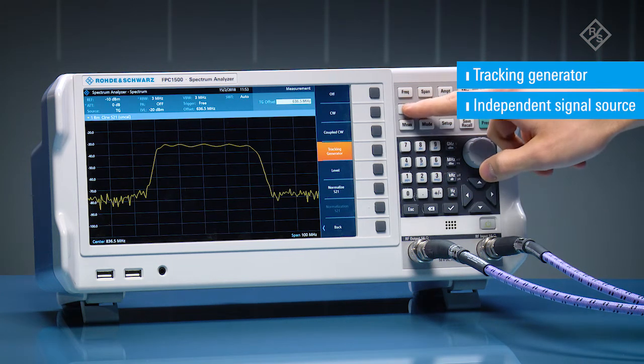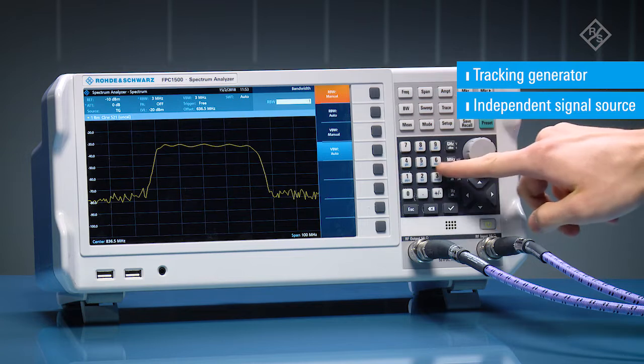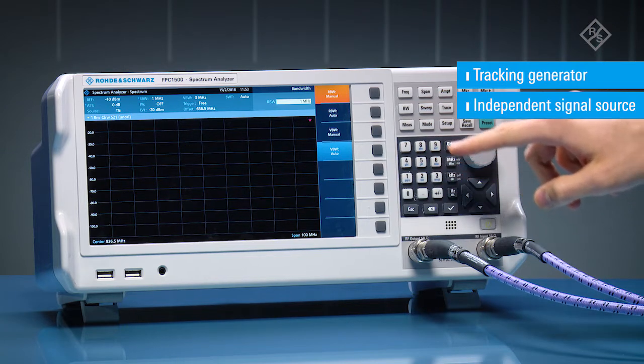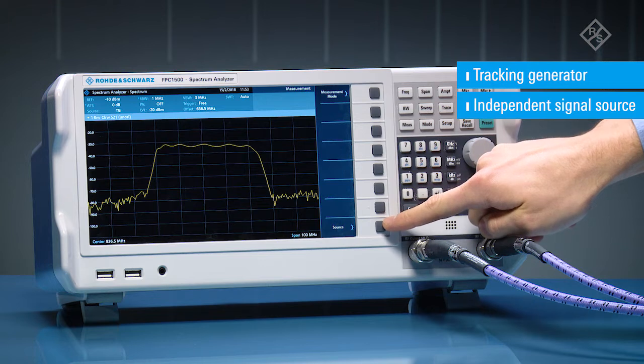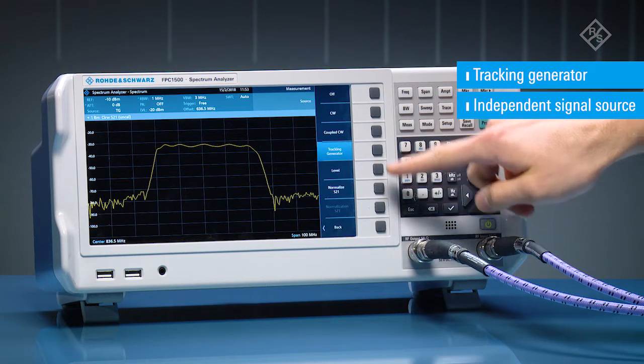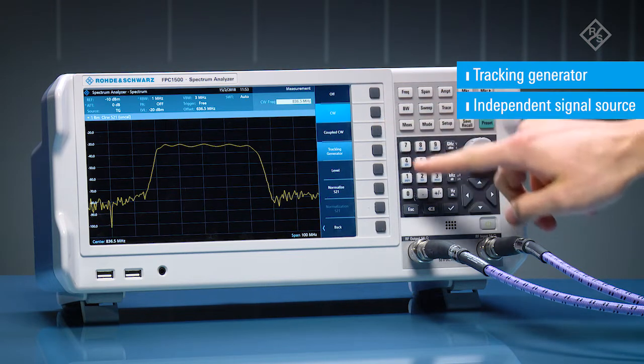The unique independent signal source of the FPC-1500 also supports signal generator functionality. Two different modes are available. One mode is used to configure a CW signal as required for the measurement setup.